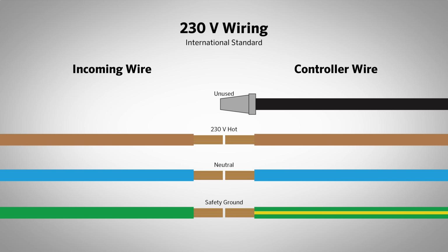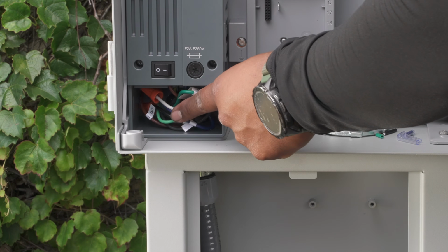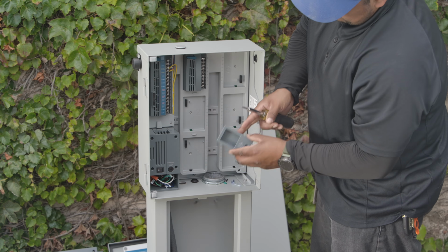In international, where 230 volt AC is commonly used, the connections are brown to brown 230 volt hot wire, blue to blue neutral wires, and green or green-yellow to green or green-yellow safety ground. The transformer black wire is not used and should be capped off securely. When these connections are made, replace the wiring compartment door and controller face pack.